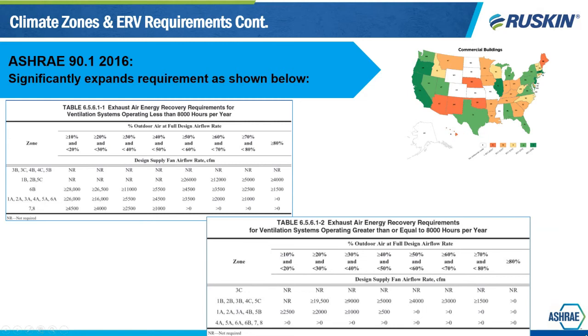They dropped the requirements down to 10% of outside air. So if you are bringing in more than 10% of outside air, you have to have energy recovery in zone 4A in all of your systems. It goes down to zero CFM. So you really see a drastic change. From 2007 to 2016, in zone 4A, you went from not having energy recovery requirements to basically being mandated to have them. So if you're not working with ERVs and energy recovery right now, with all of the changes to the code we are going to see post-COVID, I expect energy recovery to be a significant part of this moving forward.